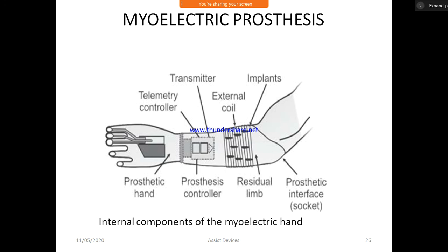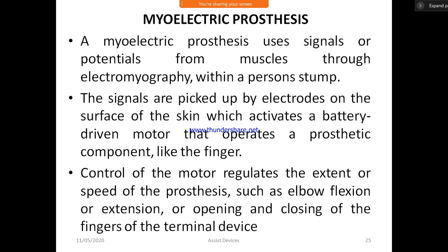The terminal device may be a functional or mechanical hand, attached to the wrist unit of most upper extremity prostheses, and operated by cable control. It consists of a plastic spring control device with fingers controlled by the control cable of the prosthesis. The thumb can be placed manually in either of two positions, to grab small or large objects. Only the thumb, index, and middle finger participate in the pinch. So that's about this terminal device.